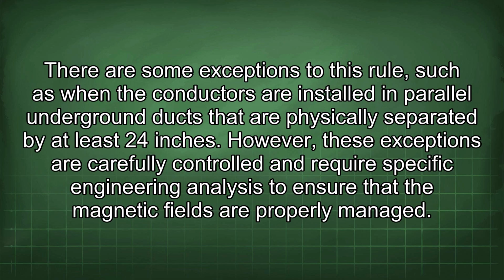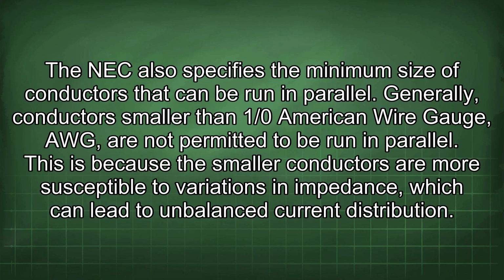There are some exceptions to this rule, such as when the conductors are installed in parallel underground ducts that are physically separated by at least 24 inches. However, these exceptions are carefully controlled and require specific engineering analysis to ensure that the magnetic fields are properly managed. The NEC also specifies the minimum size of conductors that can be run in parallel. Generally, conductors smaller than 1/0 American wire gauge (AWG) are not permitted to be run in parallel. This is because the smaller conductors are more susceptible to variations in impedance, which can lead to unbalanced current distribution.